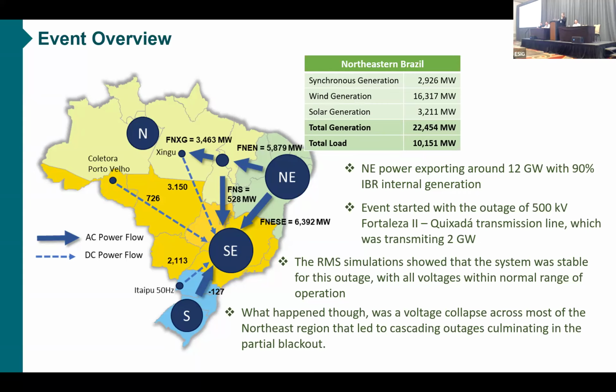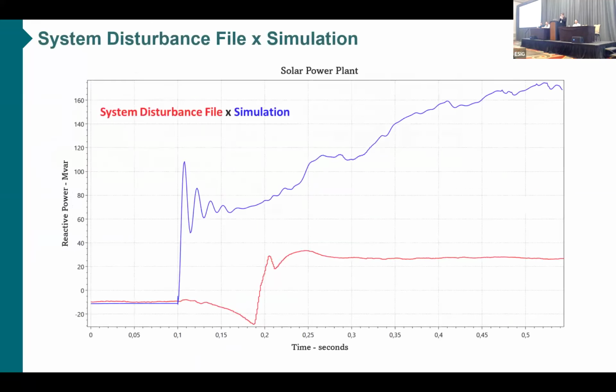Through a lot of effort, investigation, and digital fault recorder files, we identified that the main issue was with IBR performance. The simulation showed a very fast, very optimistic response, while the equipment in the field didn't. We have some examples here.